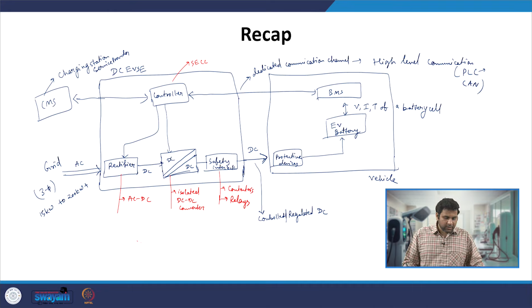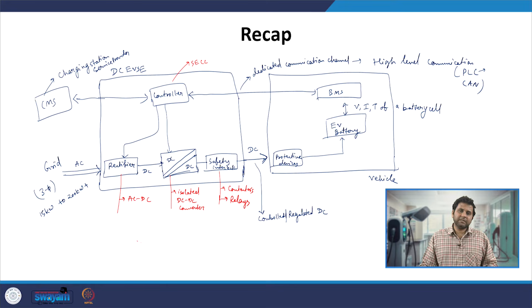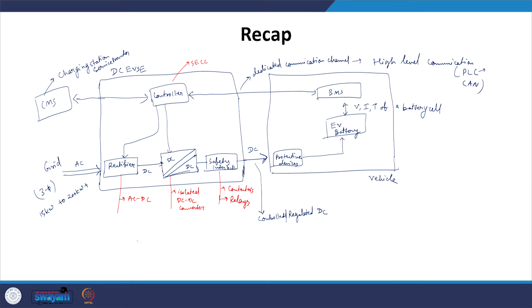On the other side, the EVSE controller, sometimes called the supply equipment communication controller, communicates with the central management system provided by the charging station provider. This helps the provider do metering, monitoring of the DC EVSEs, logging, understanding user behavior, and incorporating offers for the user. In total, DC charging has a power conversion unit with the rectifier, DC-DC converters and safety interlocks like relays and contactors. Insulation and temperature monitoring are also done, and communicated via the supply equipment communication controller, which talks to the vehicle via PLC or CAN, and to the CMS on the other side. This is how the DC charging system works.